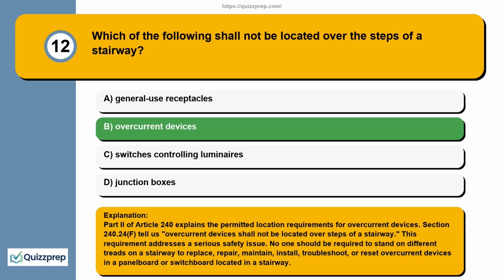This requirement addresses a serious safety issue. No one should be required to stand on different treads on a stairway to replace, repair, maintain, install, troubleshoot, or reset overcurrent devices in a panel board or switchboard located in a stairway.